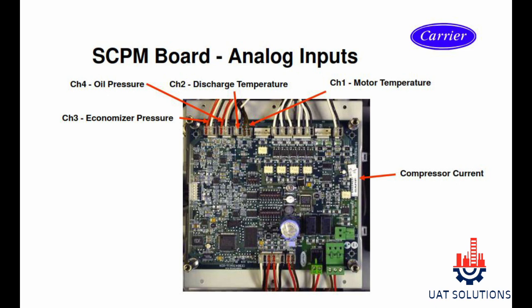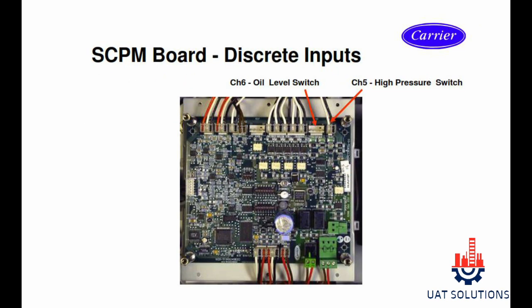Connected device connection positions are marked with arrows on the SCPM board as shown. The oil pressure sensor is connected on channel 4. The discharge temperature sensor is connected on channel 2. The motor temperature sensor is connected on channel 1. The economizer pressure sensor is connected on channel 3. The oil level switch is connected on channel 6. The high pressure switch is connected on channel 5.